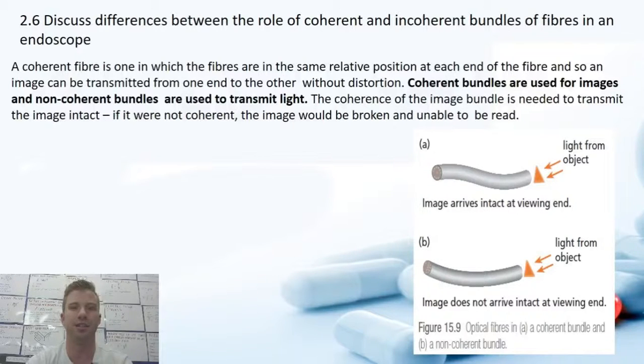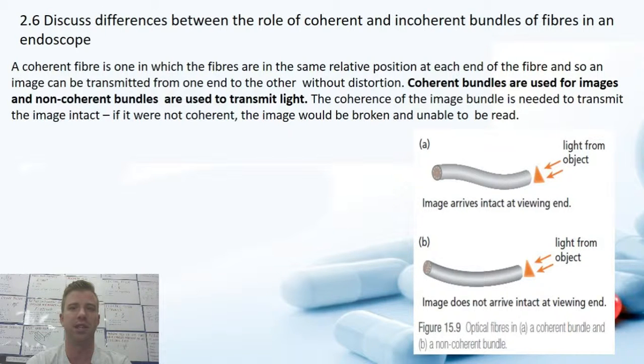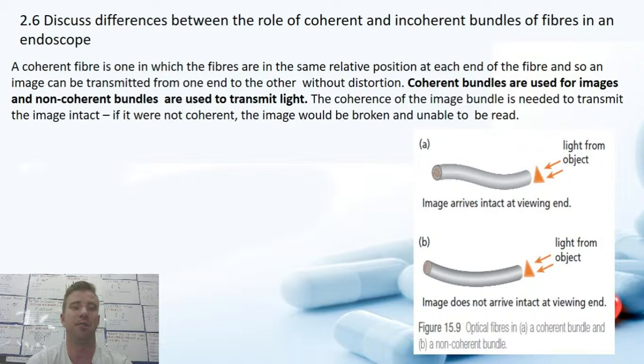2.6: Discuss the differences between the role of coherent and incoherent bundles of fibers in an endoscope. There are two differences between these: coherent bundles are used for images, while non-coherent or incoherent bundles are used to transmit light.